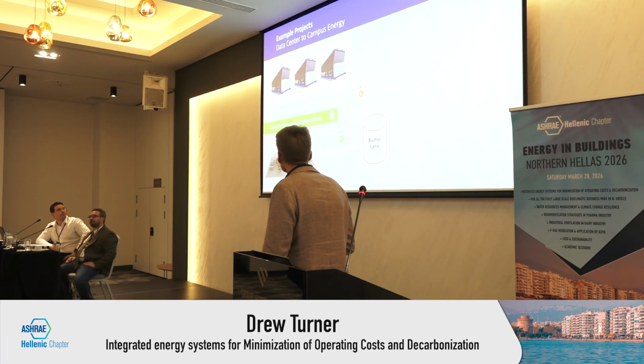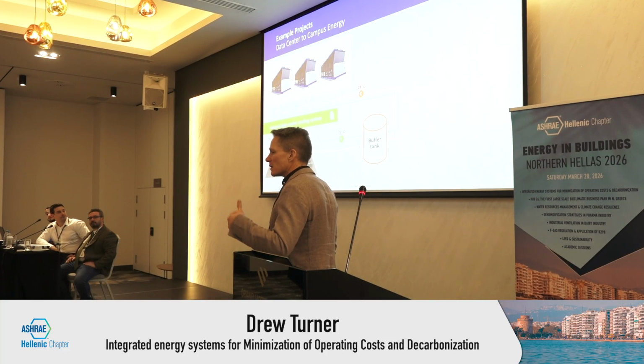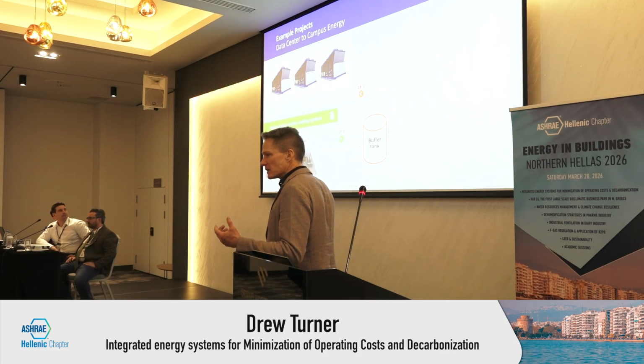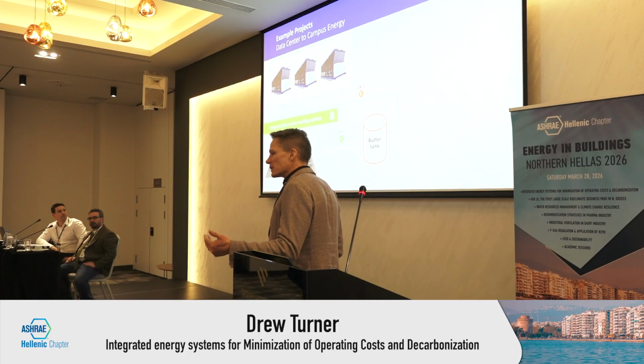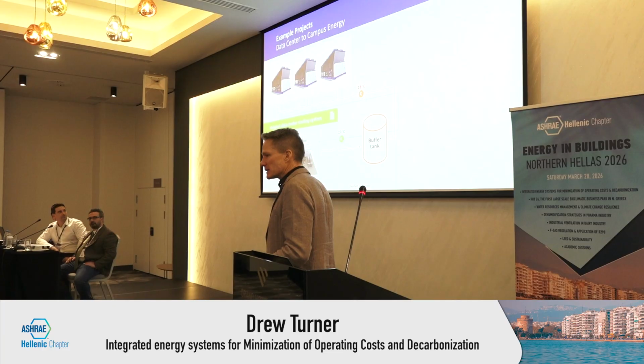There we go. This is one of the first ones that we worked on. This is a heat recovery from our own data center at our headquarters. This is right across from my office in Nordborg, Denmark, where we wanted to go in and say, okay, the other thing that we look for is everything hydronic. If the heating's hydronic and the cooling's hydronic, then you've got a relatively simple retrofit to tie those two together. And we focus on critical facilities. If you focus on critical facilities, data centers, hospitals, industrial facilities, wastewater facilities, you're almost always going to have simultaneous operation of the availability of that heat and the use of that heat at the same time.